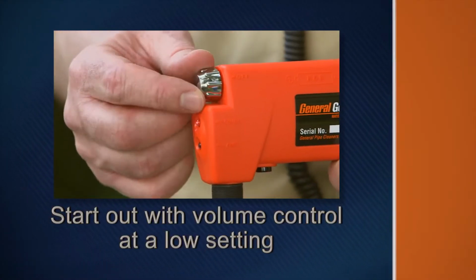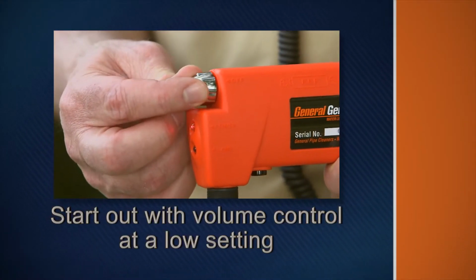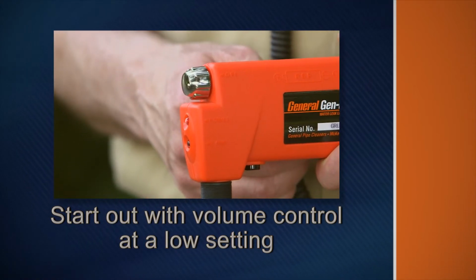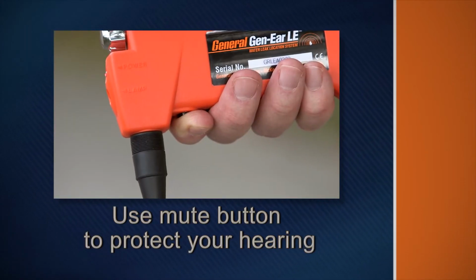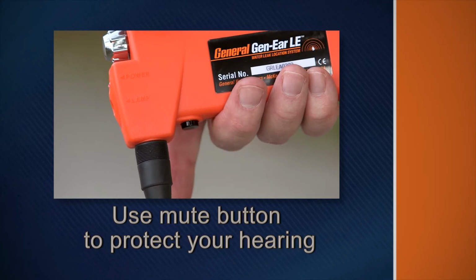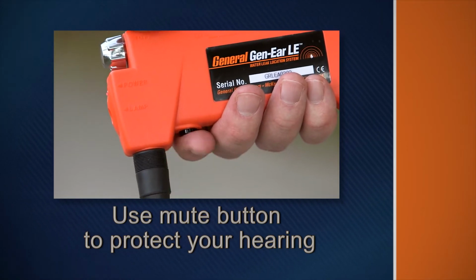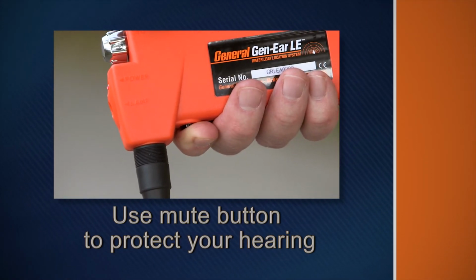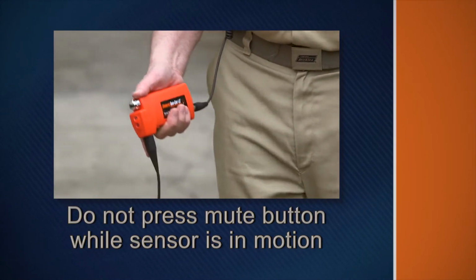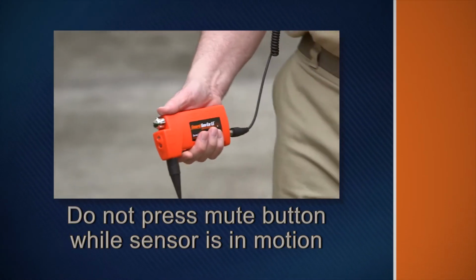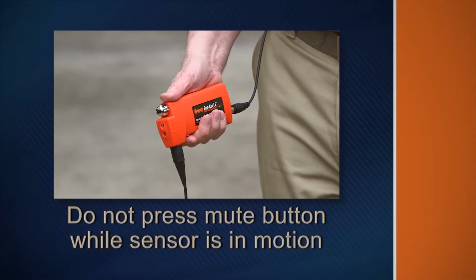Avoid possible damage to your hearing by starting out with the volume control at a low setting. Use the mute button to protect your hearing. Press the mute button when you experience sudden, loud noises. Do not press the mute button while the sensor is in motion. Wait until the sensor is in place.